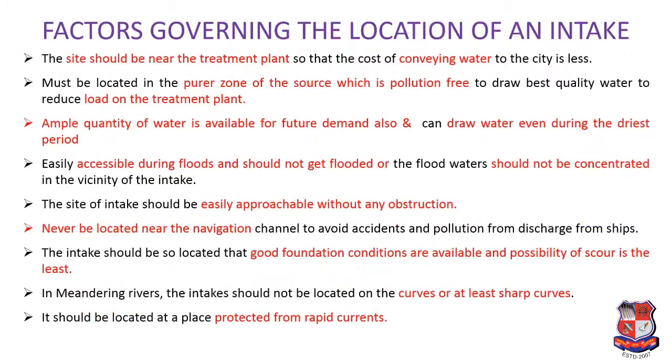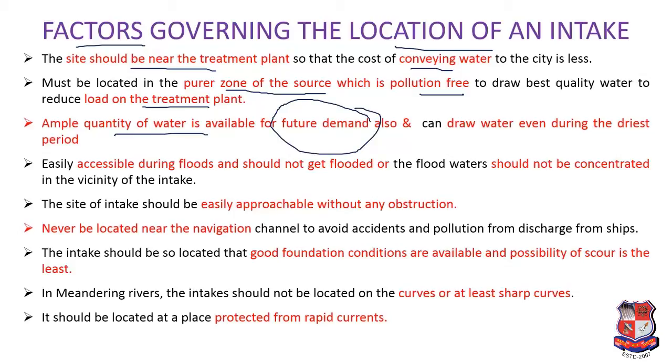If you want to select a particular location for an intake structure, you have to consider the following factors. First, the site should be nearer to the water treatment plant so that the cost of conveying water remains less. Next, it should be provided in the pure zone of the source, which is pollution free, because it will reduce the load of treatment on the water treatment plant. Next, an ample quantity of water should be available so that it can be useful for future demand also, and in the driest period also you can withdraw water.